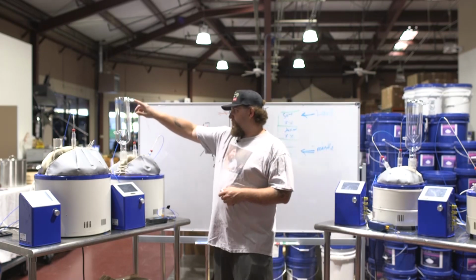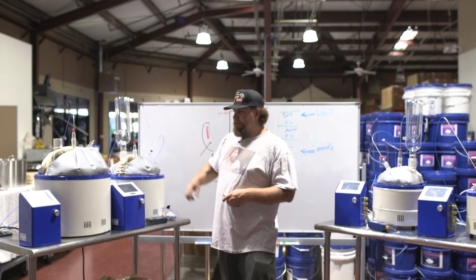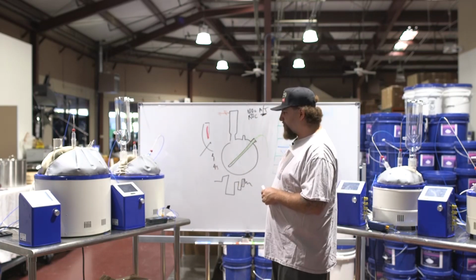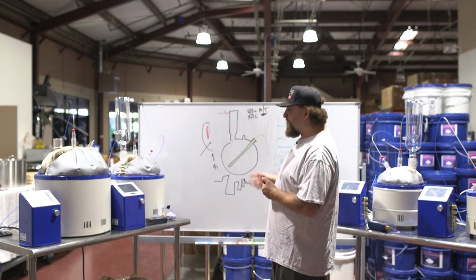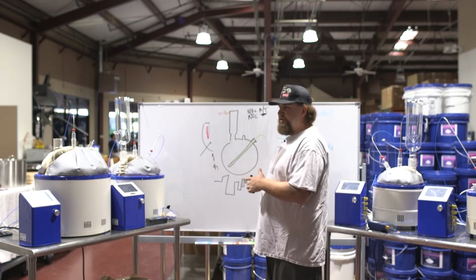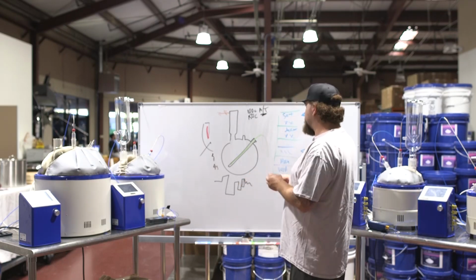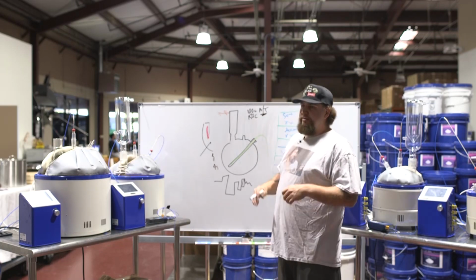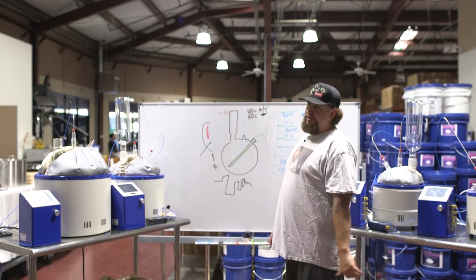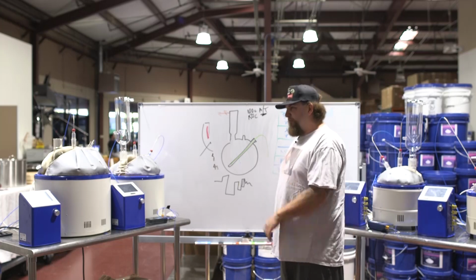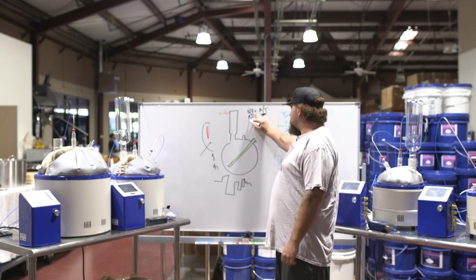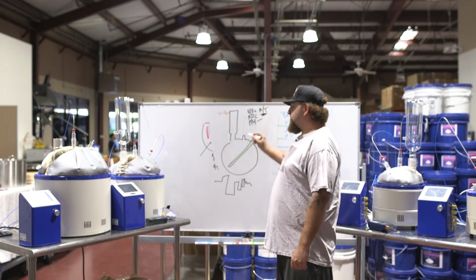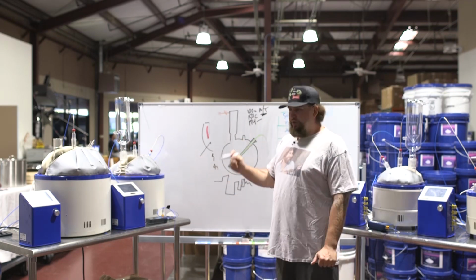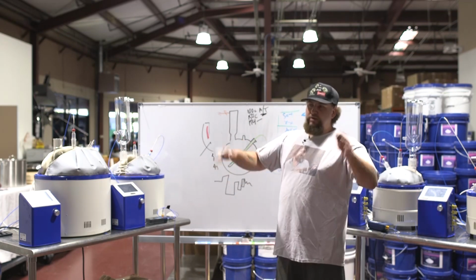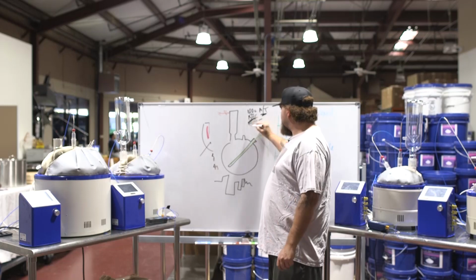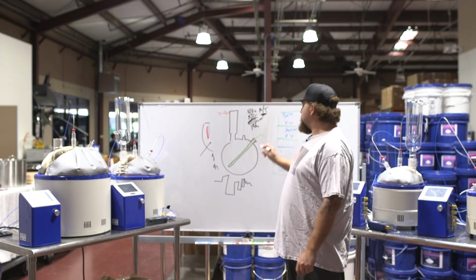I'll pull vacuum on the system from the top. I'll cap off the rest of the ports, and I'll just let it run under vacuum until all this procedure is done. Now, once this procedure is done and the auto tune is completed, basically what I do is I go to my average vapor temperature. So people think that they run 160 vapor or 180 vapor or 174 vapor. You go to 174, and that reason is because you're going to calibrate the next standard to 174. Let's just say you want to be at 185. So whatever, 185, and you calibrate to that standard.